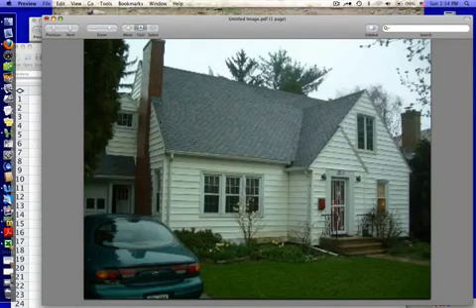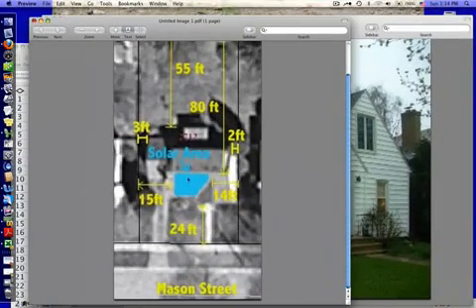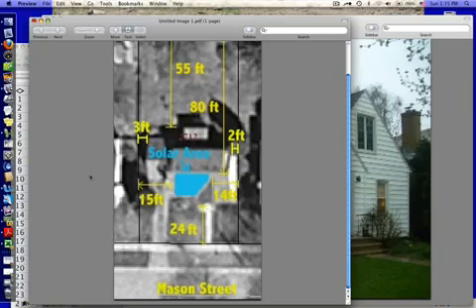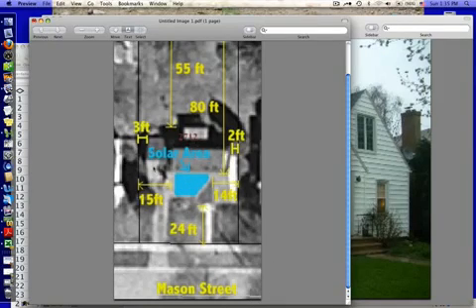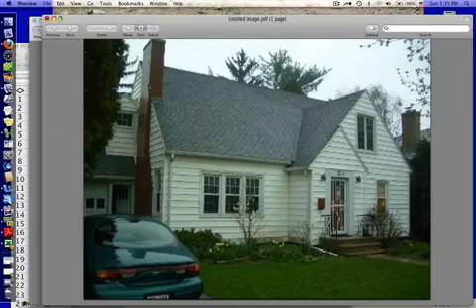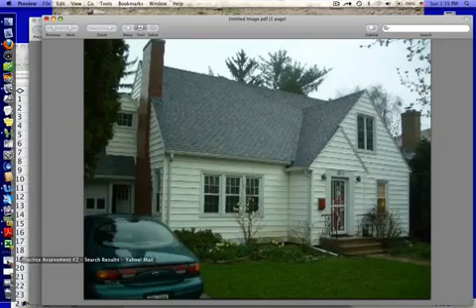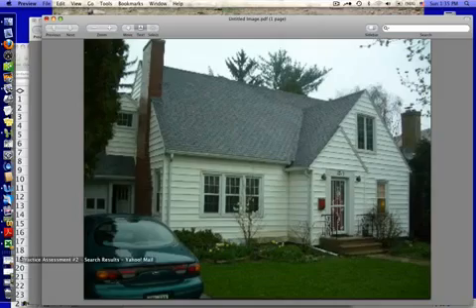We're looking at a house from the street here. I got a satellite photo from the Dane County web mapping tool and we're going to verify that we are in fact oriented on a north-south grid — the house is facing south. The blue area marks the south-facing roof area, so we are due south. The pitch is 45 degrees, which is right next to our latitude in Madison of about 43 degrees, and we're putting the solar collectors right on the roof surface.